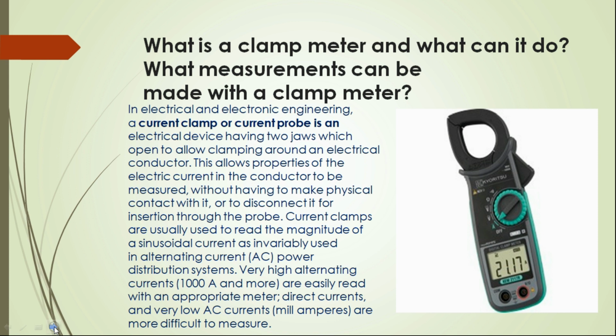In electrical and electronic engineering, a current clamp or current probe is an electrical device having two jaws which open to allow clamping around an electrical conductor. This allows properties of the electric current in the conductor to be measured without having to make physical contact with it or to disconnect it, by insertion through the probe. Current clamps are usually used to read the magnitude of a sinusoidal current and alternating current also. Very high alternating current, about 100 to 1000 ampere and more, is easily read with an appropriate meter. Direct current and very low AC currents are more difficult to measure.